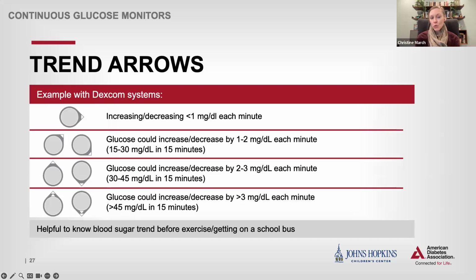I want to just talk briefly about trend arrows and what they mean. And this is an example of what they would look like using the Dexcom system. Now, again, what this is telling you is the direction that the glucose is changing, as well as how quickly it is changing. So one arrow slightly up or slightly down indicates that the sensor is detecting a change in glucose of 1 to 2 milligrams a minute. And I think easier to understand, that means it may differ by 15 to 30 milligrams per deciliter in 15 minutes. An arrow straight up or straight down is a 2 to 3 milligrams per deciliter change per minute, or 30 to 45 milligrams per deciliter in 15 minutes.